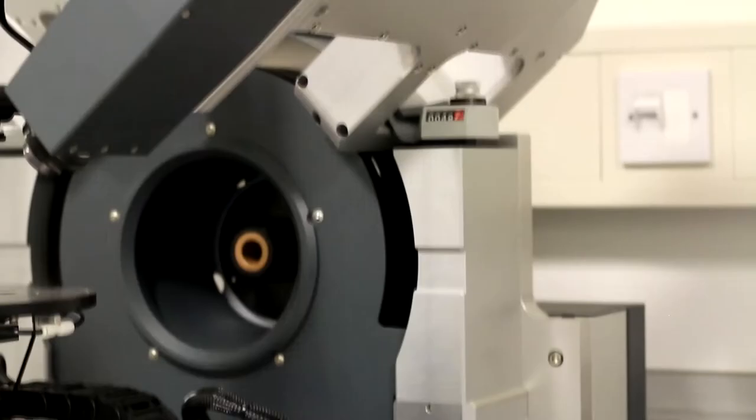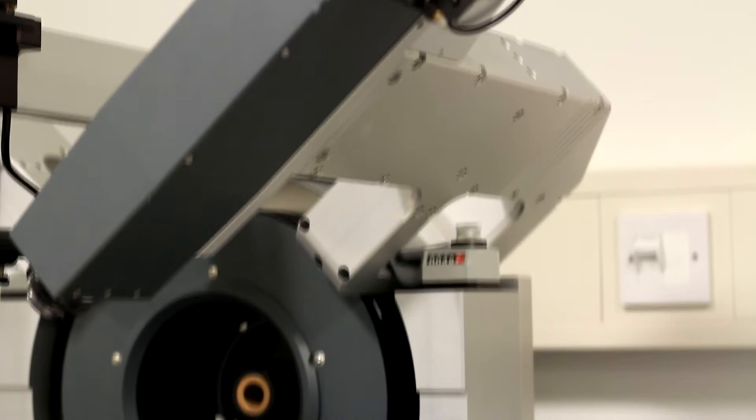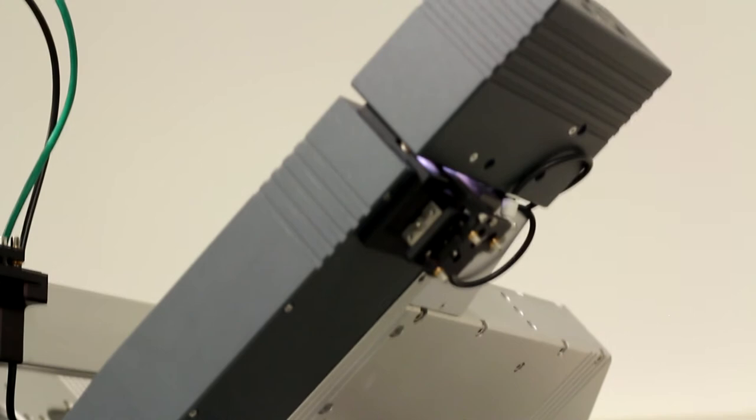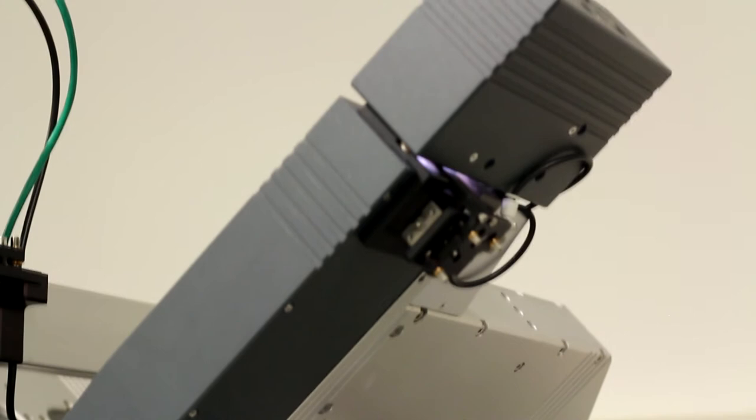The analyzer arm consists of a system of optics, a rotating compensator, and UV, VIS, and NIR detectors. This allows for the measurement of phase and polarization changes in the light following interaction with the sample, from which the sample optical properties can be modeled.